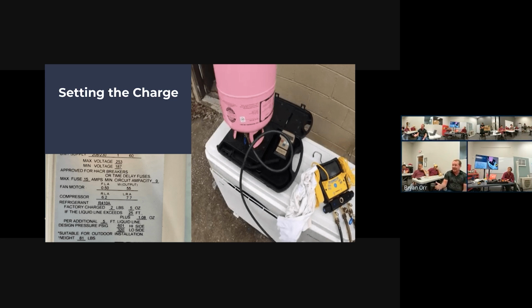But the rest of it has to be designed for the high side pressure, because in heat mode, the indoor coil is the condenser. Does that make sense, what I'm saying here? So in heat mode, that inside is going to see that high pressure anyway, so it is on the high side of the system. So they kind of make it confusing with that.